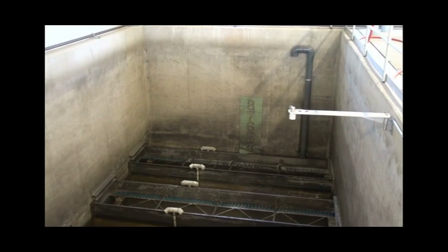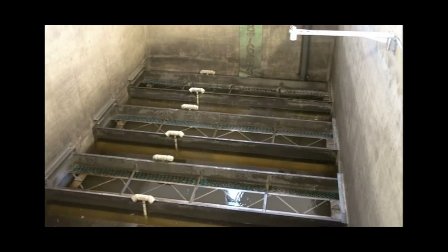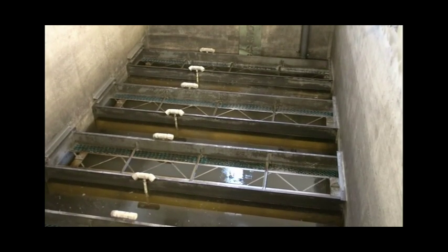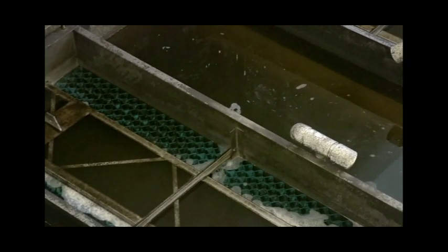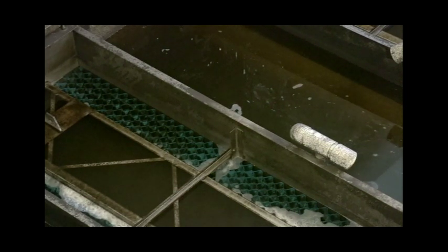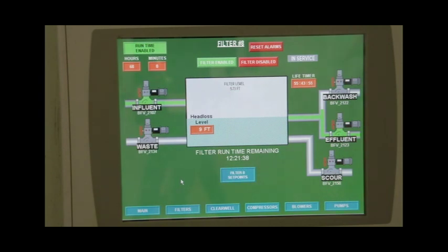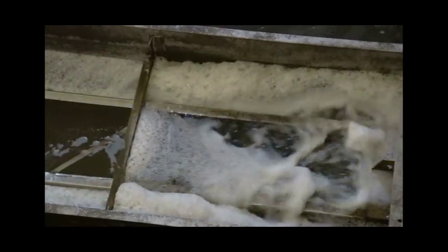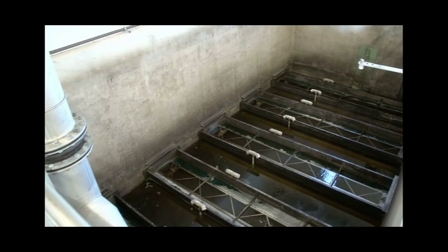As the water leaves the final clarifiers, it flows into the effluent filters where the remaining solids are strained out by the filter media. The water flows through eight filter cells that contain almost three feet of anthracite in each cell. The wastewater flows through a series of troughs and is evenly distributed over the filter media where it flows down through the media. These filters are controlled by a new computer that is programmed to clean each filter during the evening hours. The computer automatically opens and closes all the right valves to take filters out of operation and clean them. It also turns on a water pump and air blower to force water and air through the bottom of the filter media, washing all the solids caught in the media back to the front of the plant where they eventually work their way towards the digesters.